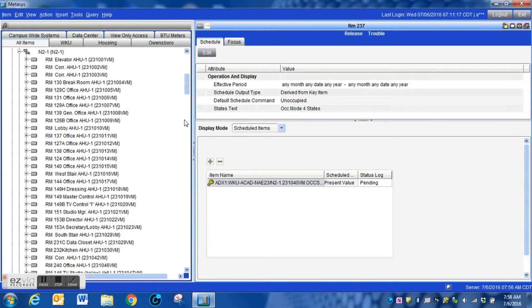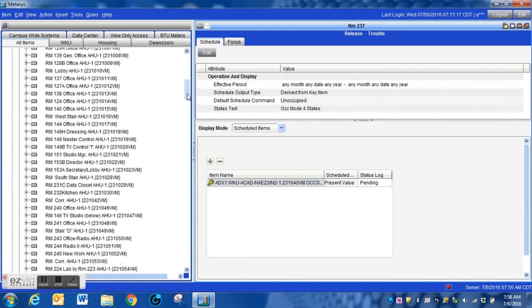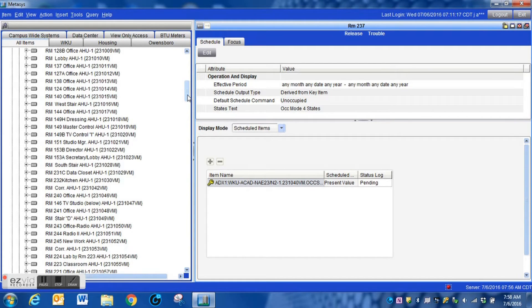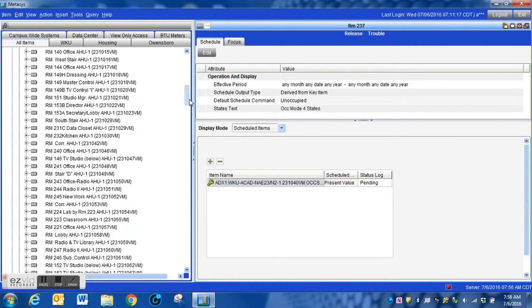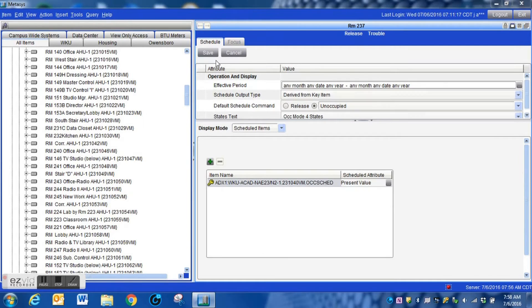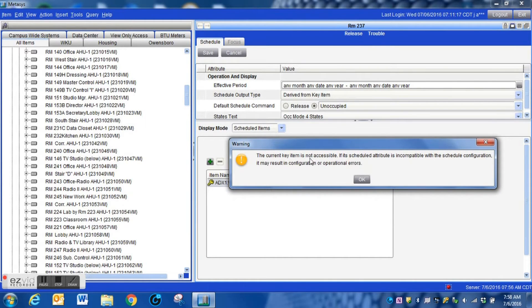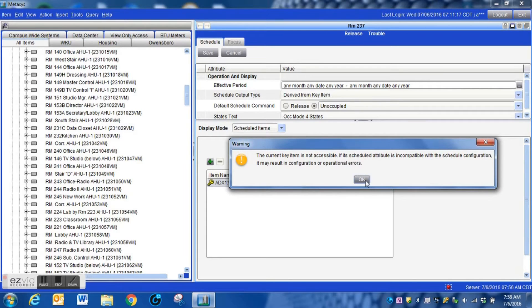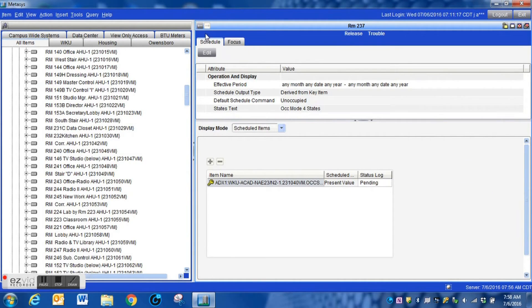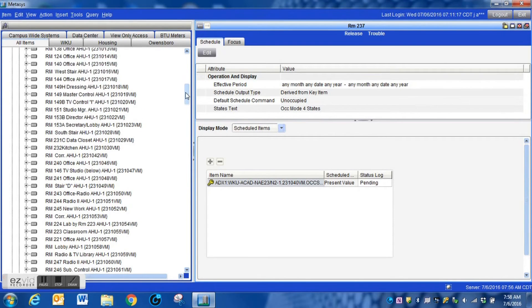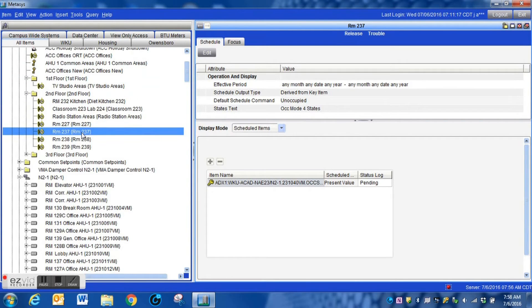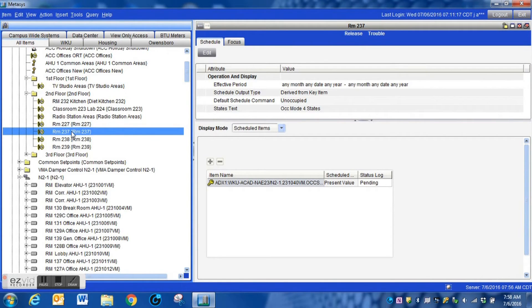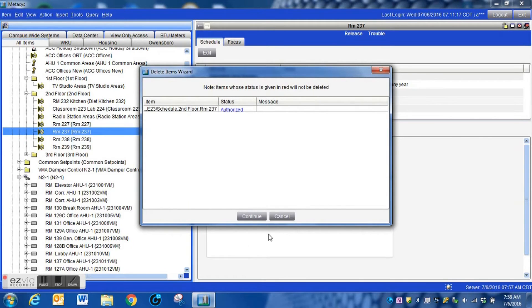We go back to the All Items tab and verify that it is a controller that no longer exists — we look through the trunk just to make sure, and we clearly do not have it there. When I press the Edit button and try to make any changes, it tells me there is an error. So we cancel, verify it no longer exists, highlight it, hit Delete, and simply remove the schedule from the system completely.